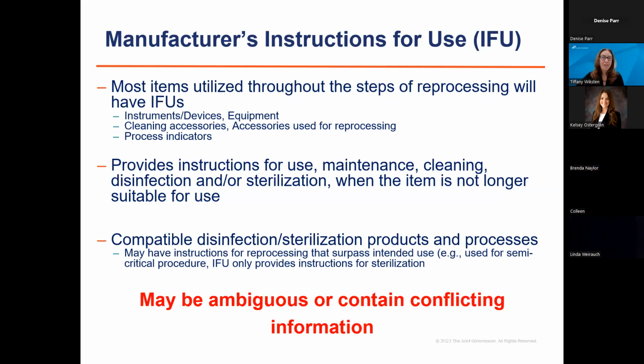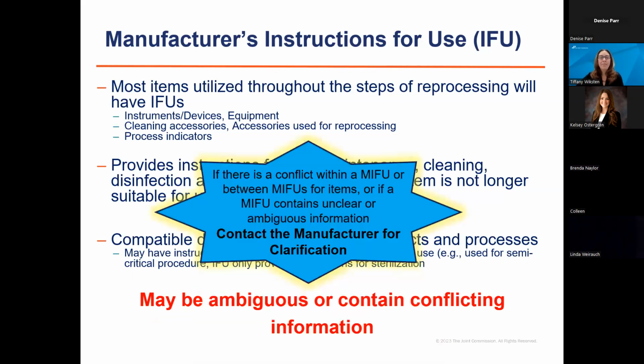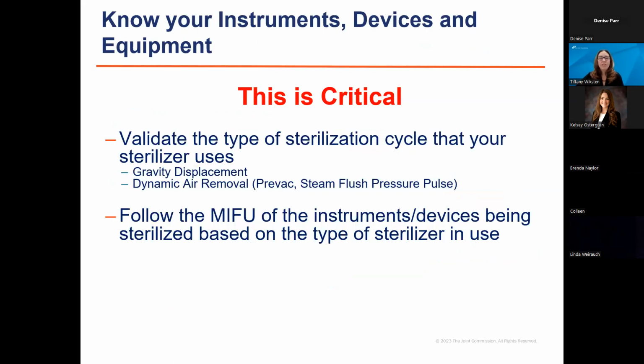Your manufacturer's instructions for use may also be ambiguous or contain conflicting information. So if you don't know what they're telling you to do, if you're unclear, or say your manufacturer's instructions for use, it's a vaginal probe, right? We know it's coming into contact with mucous membranes. They don't have instructions for high-level disinfection or sterilization. You need to contact the manufacturer for clarification. So if there's a conflict within a manufacturer's instructions for use or between manufacturer's instructions for use for items, so between an instrument being sterilized and its sterilization accessory being used, so a pouch, a wrap, or a container, or if the manufacturer's instructions for use contains unclear or ambiguous information, contact the manufacturer for clarification and obtain their response in writing. So this is really, really, really critical.